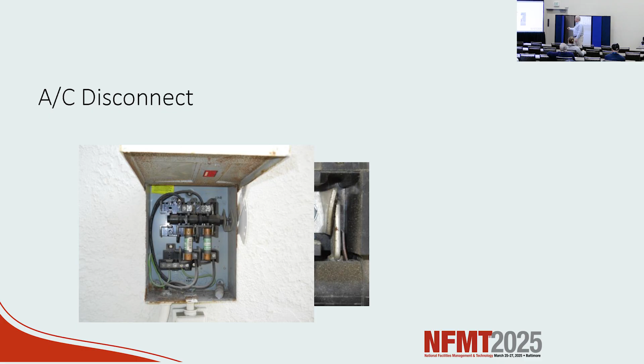This is a splice on a knife switch, single phase. The point is showing a 230 degree knife switch with a problem, and this does exist. I had a very large hotel chain in Palm Springs, California, where I did this on their main chiller and found a 300+ degree fault, in the heat of summer. When you've got two plants running the whole facility and one goes down in the heat, something hits the fan. Knowing the problem before it happens is the key and the goal.